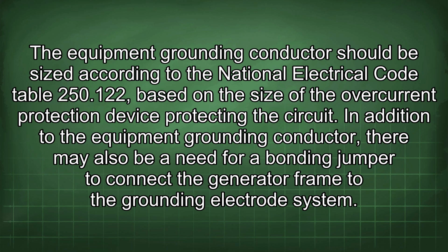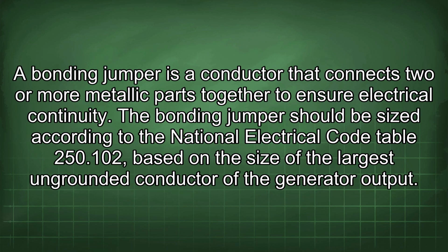In addition to the equipment grounding conductor, there may also be a need for a bonding jumper to connect the generator frame to the grounding electrode system. A bonding jumper is a conductor that connects two or more metallic parts together to ensure electrical continuity. The bonding jumper should be sized according to the National Electrical Code Table 250.102, based on the size of the largest ungrounded conductor of the generator output.